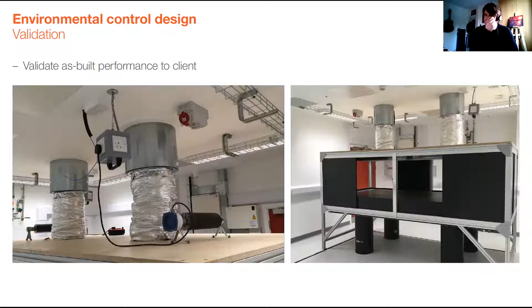In the image on the left, you can see we put some tubular heaters in the room, placed in the same spots where scientists said they would put heat-emitting equipment, to simulate an in-use heat demand. We turned the system on, turned the heaters off and on, then did the same in the lab next door, and the lab after that, monitoring each lab and whether it was able to perform.